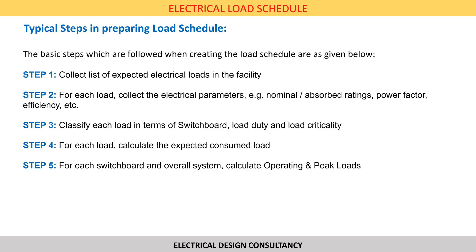First, we need to collect the list of expected loads in the facility. Then for each of these loads we need to collect the electrical parameters, namely the nominal and absorbed power, the power factor, and efficiency. After this, we need to classify each load in terms of switchboard, the load duty and the load criticality. As a next step, we need to calculate for each of these loads the expected consumed load.